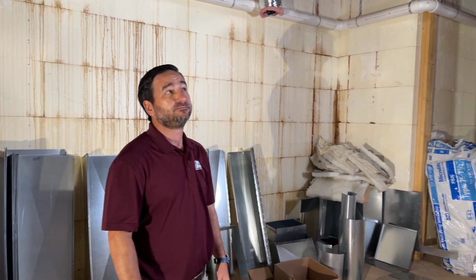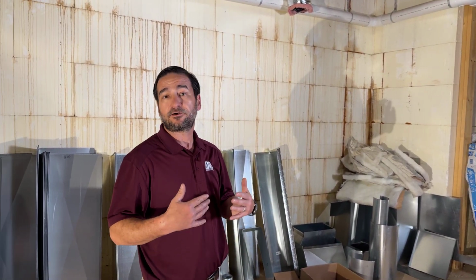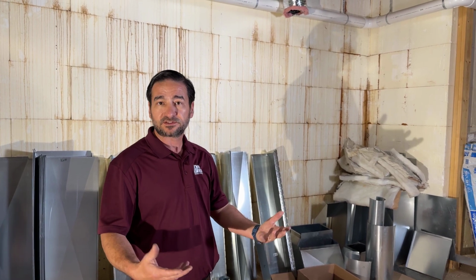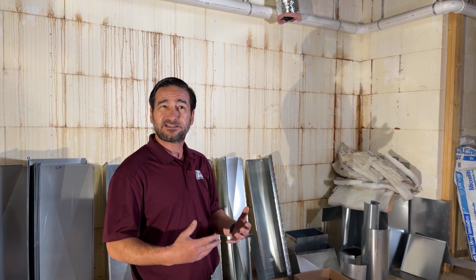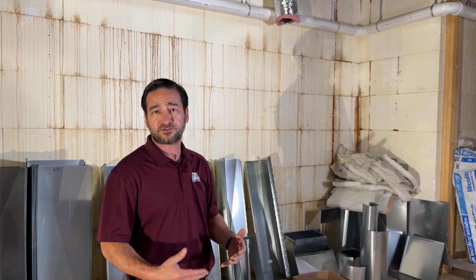One is that you seal the duct system, because when you only have one zone calling, you will increase the pressure in the duct, so any leaks that exist will be exaggerated and be even more leaky. That would make for uncomfortable basements that are already going to be cold just because the cold air wants to fall. The other thing that you want to do is you typically are going to oversize the trunks.